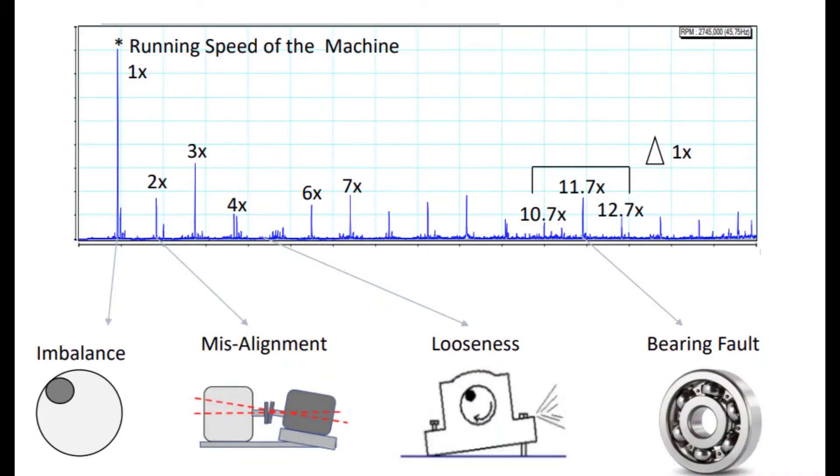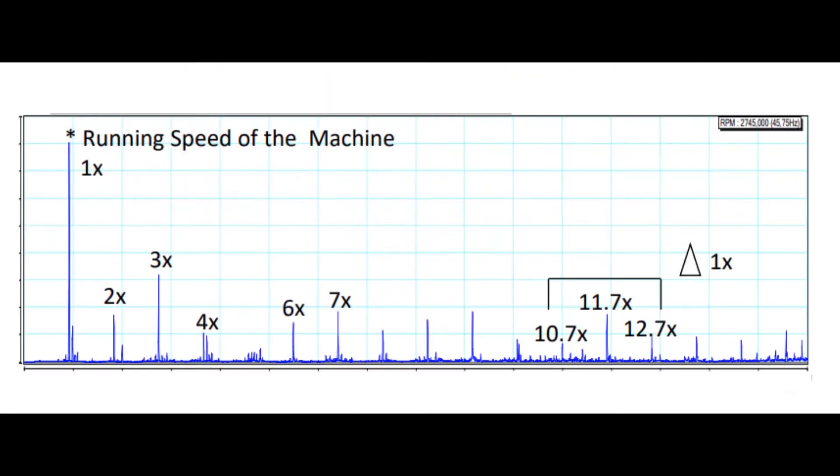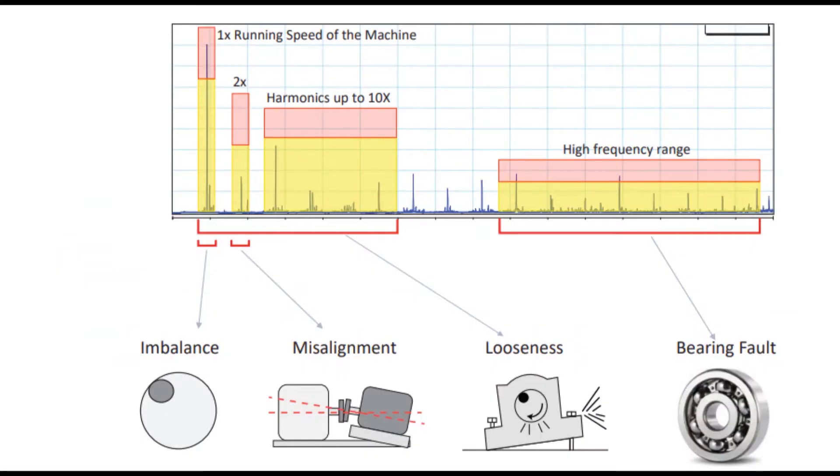Vibration analysis is an effective way to analyze frequency graphs to determine a fault using pattern recognition. But just like an EKG has a lot of information, it often takes a trained and experienced analyst to unlock the answers. Narrow band alarms look for patterns of mechanical faults and ignore noise from structures, resonances, and the process.